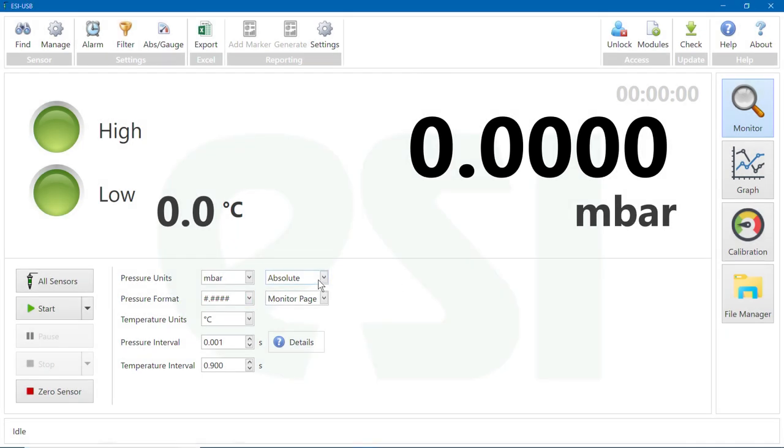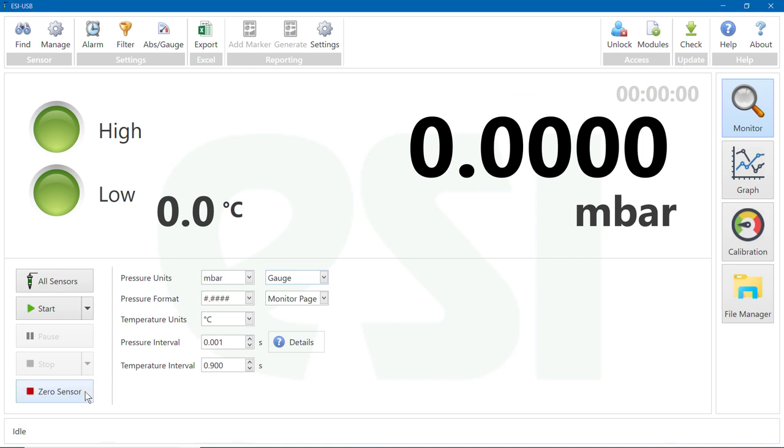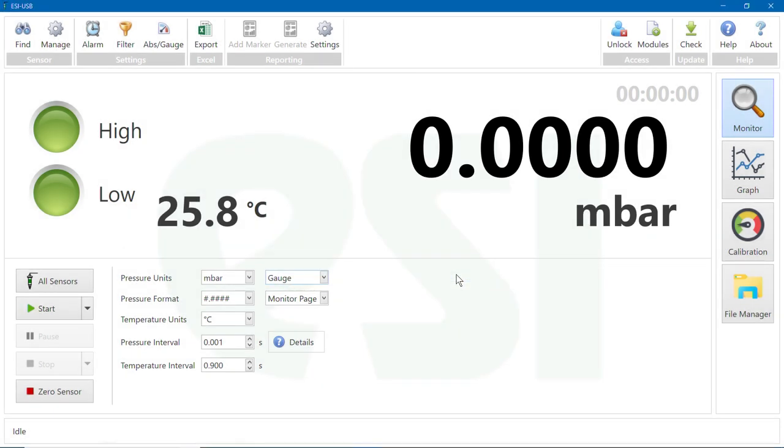For normal use, select Gauge from the drop-down menu. Click on Zero Sensor to remove any offset error. The screen will confirm the sensor selected and whether you want to zero the sensor. Click Yes, then OK when the sensor has zeroed. This should be done before each test.